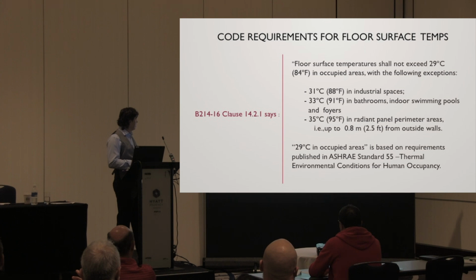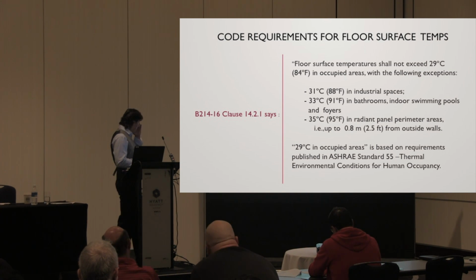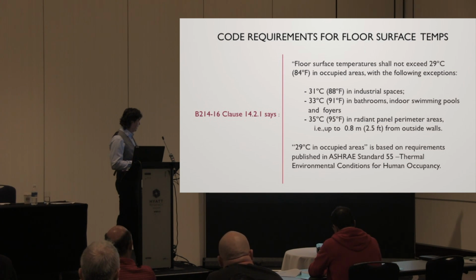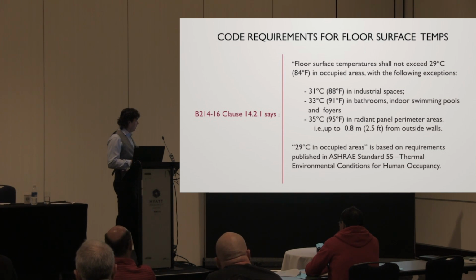Okay. So now we're talking about all these circulating temperatures. Yeesh. Okay, let's talk about the code. B214, that's CSA. It says floor surface temperature shall not exceed 29 degrees C, 84 degrees F, in occupied areas, with the following exceptions. Industrial spaces, well, we're not concerned about that really. But bathrooms, you could be 91. Indoor swimming pools and foyers. In radiant panel perimeter areas. Well, that's interesting. Apparently, you're not going to be standing in those.